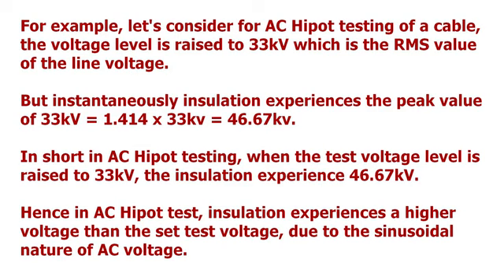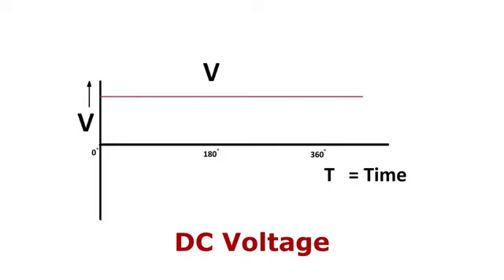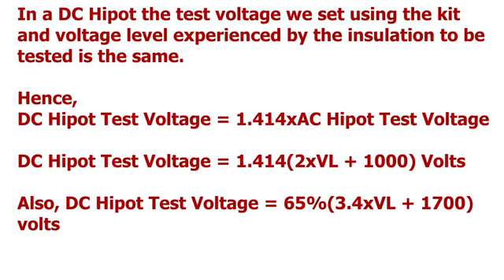But instantaneously the insulation experiences the peak value of 33 kV, which is 1.414 times 33 kV, equal to 46.67 kV. In short, in AC high pot testing, when the test voltage level is raised to 33 kV, the insulation experiences 46.67 kV. Hence in AC high pot test, the insulation experiences a higher voltage than the set test voltage due to the sinusoidal nature of AC voltage. Hence, considering the point we just saw, DC voltage remains constant with time and does not have peaks like AC voltage. So, in DC high pot, the test voltage we set using the kit and the voltage level experienced by the insulation to be tested are the same.